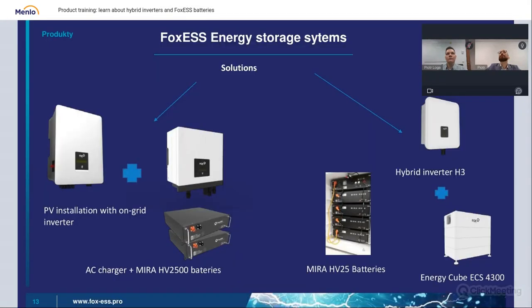Let's talk a bit about our products. Our main solutions for today are, let's say, dual. The first solution is a retrofit. When you have an operating PV plant with a standard on-grid inverter, using our set, you can add an energy storage system in a capacity of your choosing, without even taking down the on-grid inverter. Our retrofits, our chargers, are connected directly to the AC grid, so they don't need a direct connection or communication, nor power connection with the inverter.